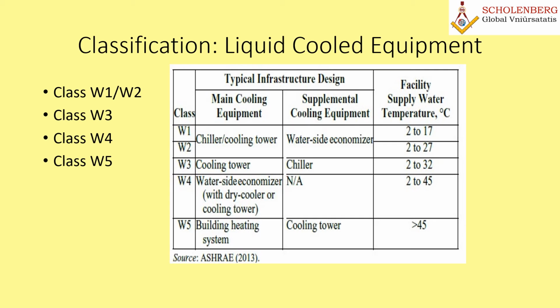Of course, these data are given only by the datacom equipment manufacturers, but mostly if you find class W1 or W2, it is very common where the load density is very high. But again, as I said, you may encounter mostly air-cooled equipment only. The availability of liquid-cooled equipment for data centers, compared to air-cooled equipment, is very rare because only very high load or very big data centers apply this. So for simplicity, you may concentrate only on air-cooled equipment as of now. But this is additional information, you can have it.